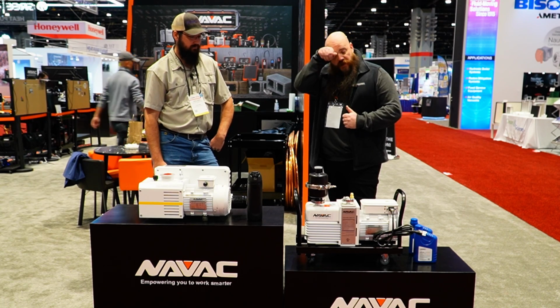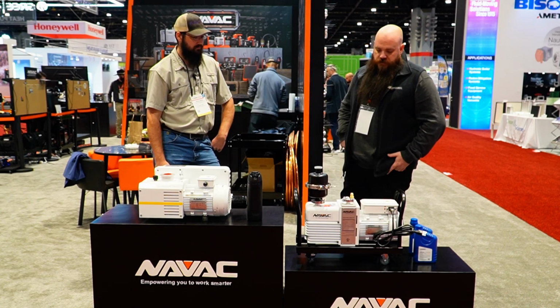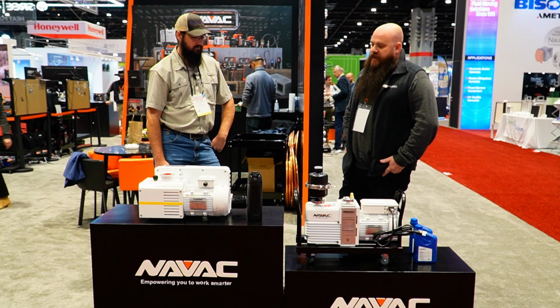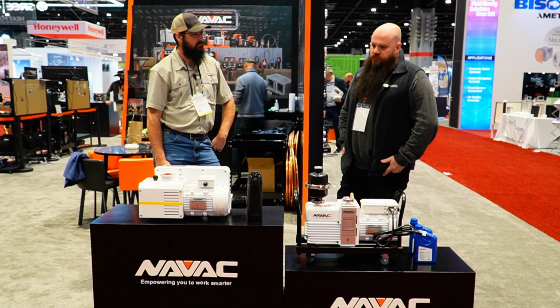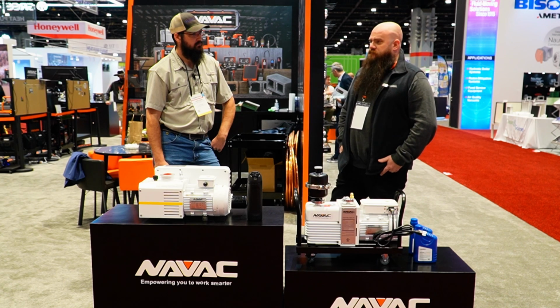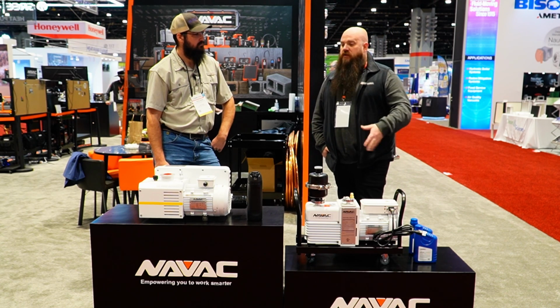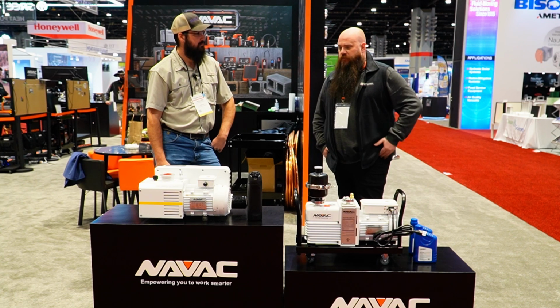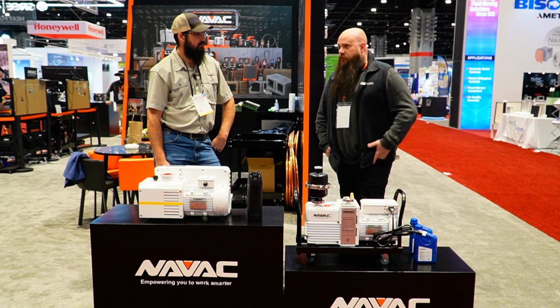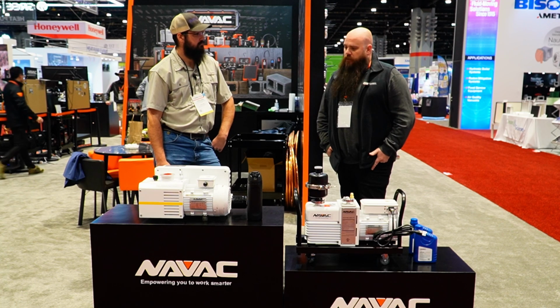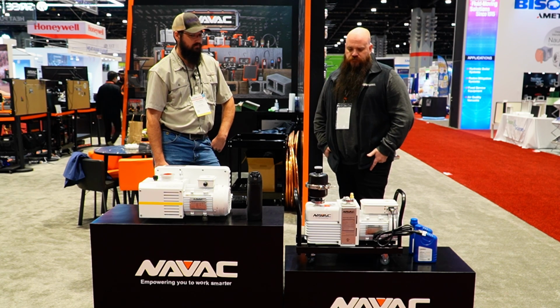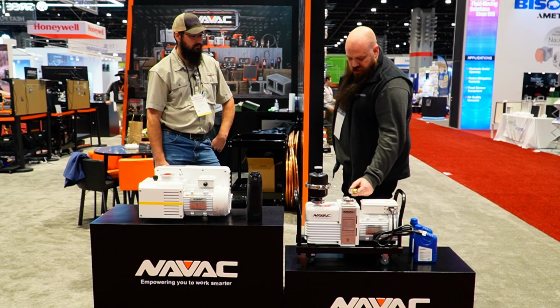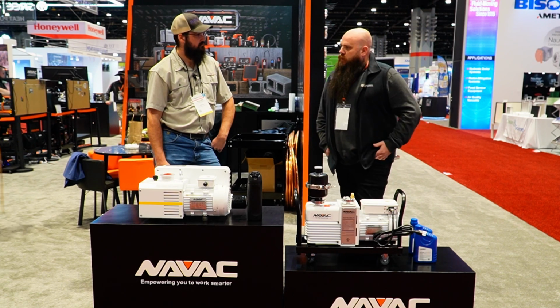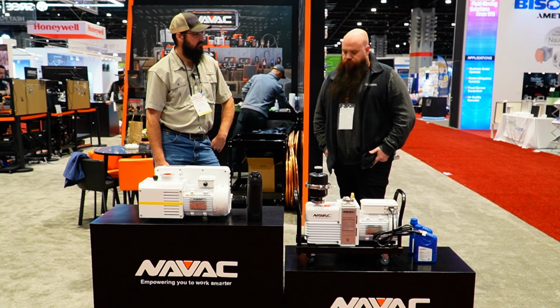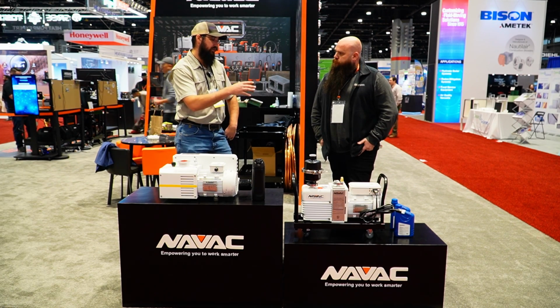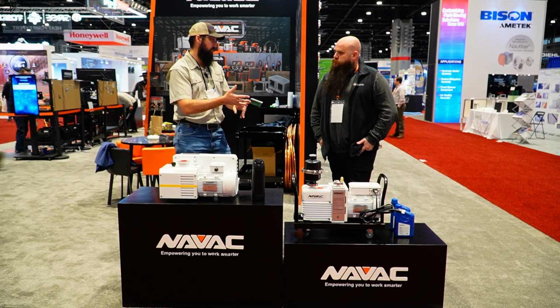But typically the standard on an industrial style pump is going to be that KF flange. I think I said KF15 before in the video and misspoke - it's KF25. So KF25 would be your typical industry standard internationally for these types of products. Going with a typical hose is a little bit outside of the norm in a broad sense, but on the outside of the 16s, you've got the 24 and the 30 as well.